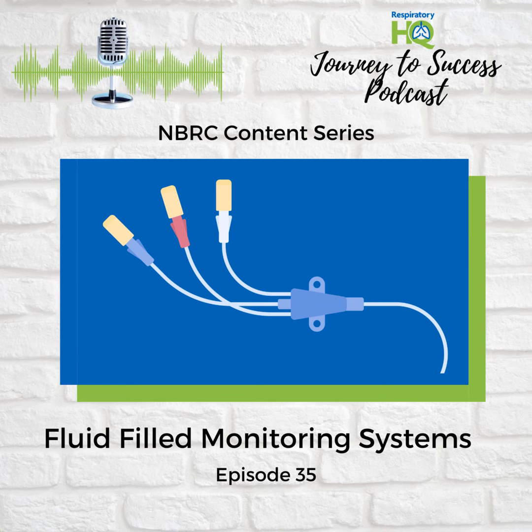And our source also talks about square wave testing. What's that all about? Oh, that's a good question. Square wave testing is basically a quality control check. It makes sure the system is accurately representing the pressure waveform. Got it. It's like sending a brief, square-shaped pressure pulse through the system and seeing how it responds. Yeah. It's making sure the natural frequency and damping characteristics are within acceptable limits. And that brings us to the concept of hemodynamic pressure. Okay, things are getting interesting. Right. So the pressure we're measuring is hemodynamic, which means it's constantly changing because of the beating heart. But this constant change introduces a challenge.